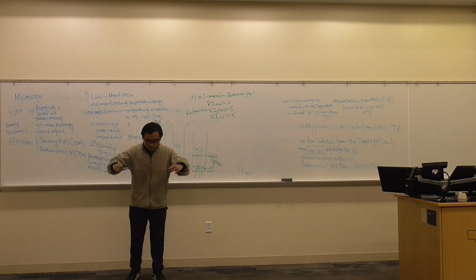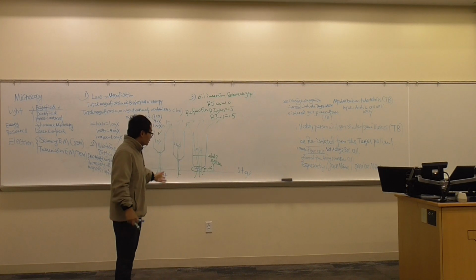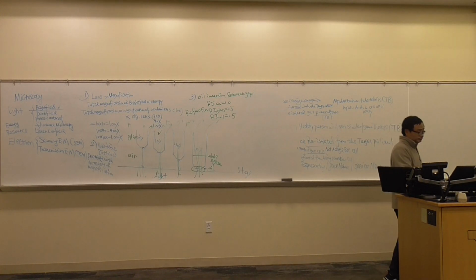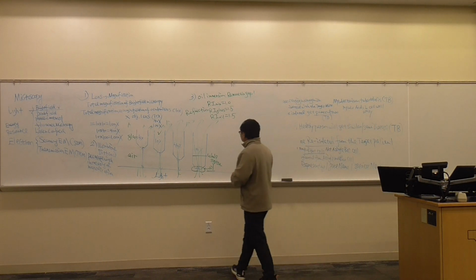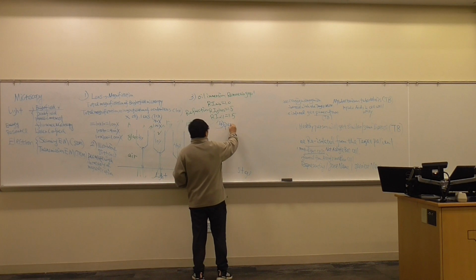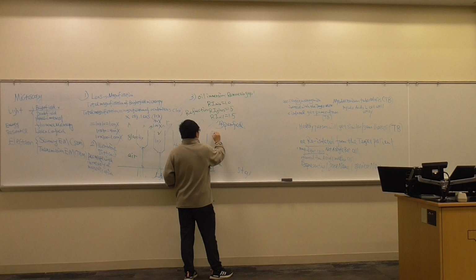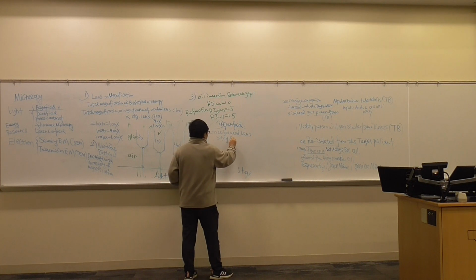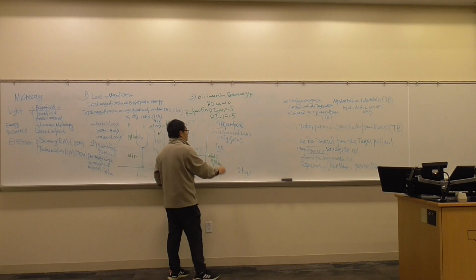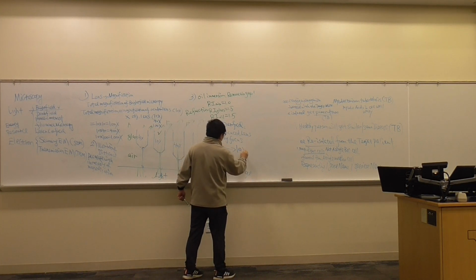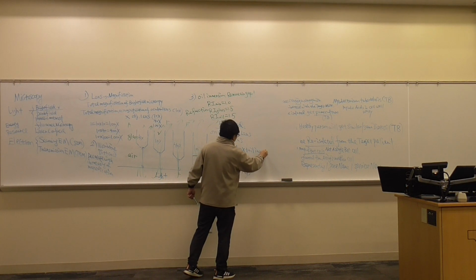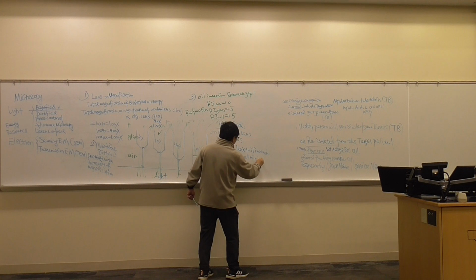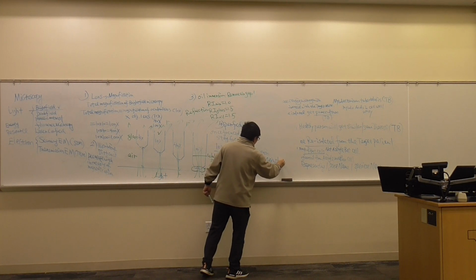Lots of people switch to doing this, doing that, using the fine focus or coarse focus. And I want to tell you one thing. This type of bright field microscope doesn't have this problem. Why? Because they have a very good characteristic called parfocal, which means once focused, the lens stays focused. This means if you're using 10x to find a specimen, and you transfer to 100x with oil immersion, you only need minimal adjustment. You will get the job done.